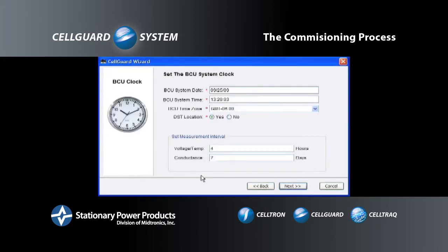On this screen, the Cellguard System date, time, and the measurement interval time is set. The Wizard will populate the date, time, and time zone from the PC you are using for commissioning. If you are not set for the correct date and time, or you are in a different time zone, change it to the correct settings. Midtronics recommends that you use the default measurement interval times of voltage and temperature every 4 hours and conductance every 7 days. If altered, these settings may impact system performance.